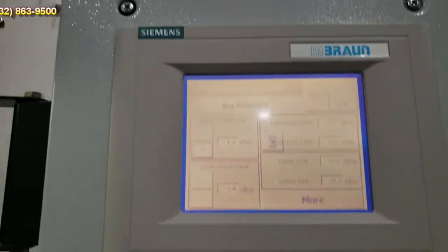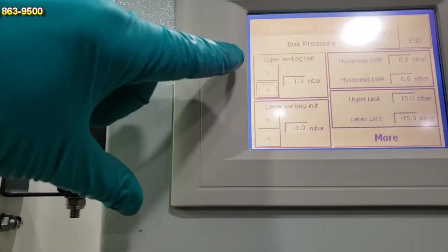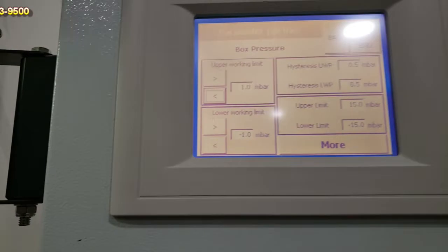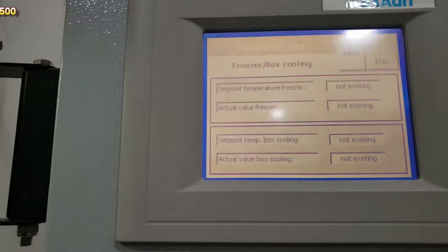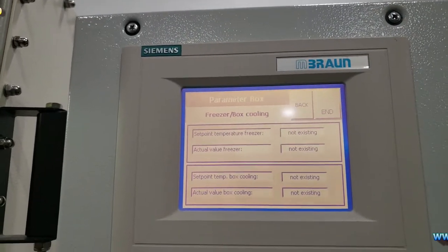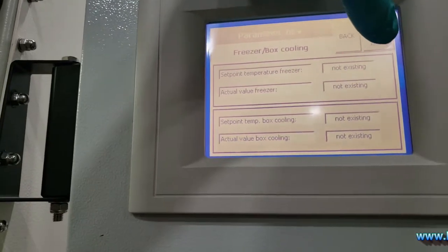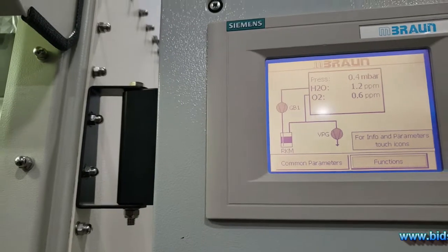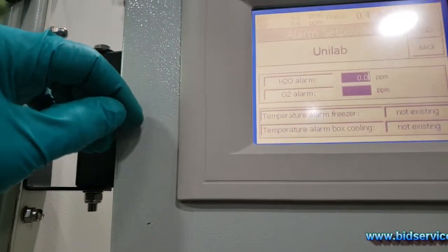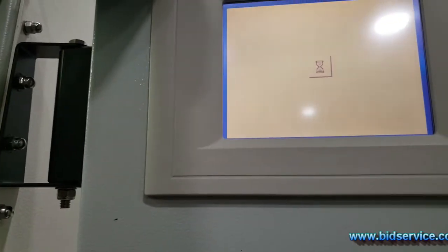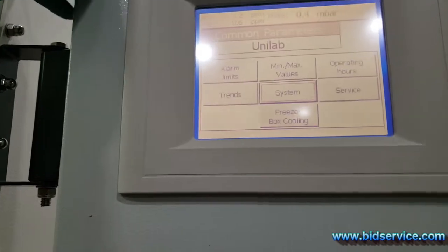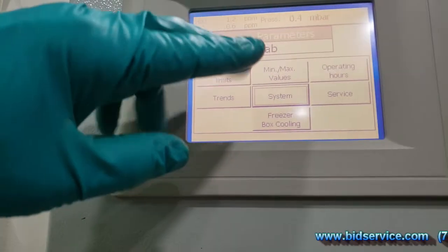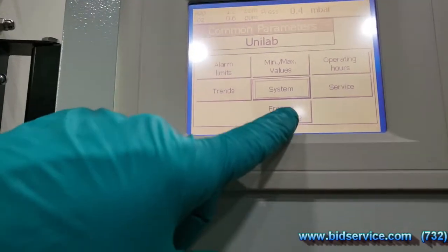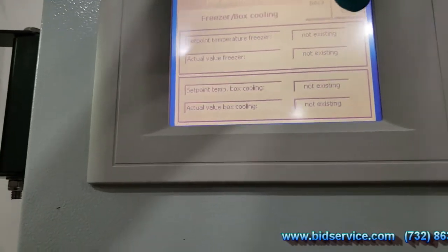To set the parameters of your pressure inside the box, you hit the icon there, and you can see your working limit. I have the upper set to 1, lower to -1. Hysteresis, upper and lower limits. You go to more, and you see none of this exists on the box. There's no freezer and no cooling on the box. Hit end, you get back to your main screen. Common parameters, just cover that real quick. You set your alarm limits, for instance, here. And again, all of this is explained in the manual. What else do we have in common parameters? Max values, operating hours, trends, system, service. No cooling is available on this system. So we'll just go ahead and hit end.